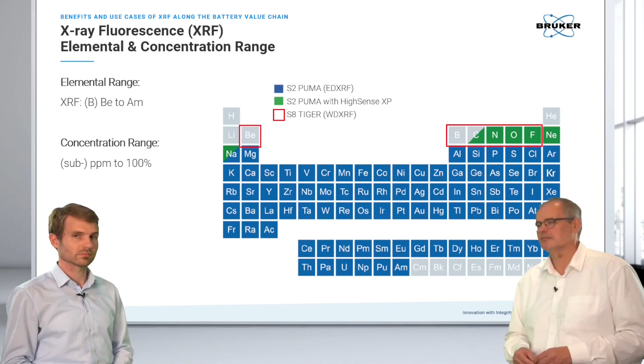Yeah. There are some gray elements we cannot analyze directly, but there are ways even to see and to evaluate those non-measurable elements. For example, the rest to 100, or the Compton ratio. This is the scattered radiation coming from the X-ray tube, which tells us about the general sample composition. So we can access also non-measurable elements, or by stoichiometric ratio. Therefore it also helps to work for lithium or oxygen, right?